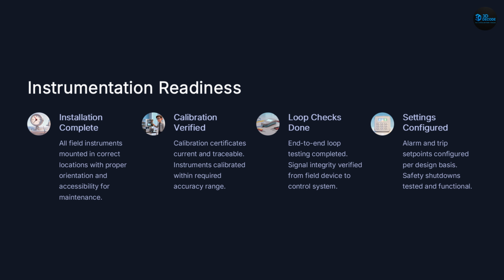instrumentation. The first requirement is installation. Every instrument must be mounted correctly, accessible, properly oriented, ready for operation. Then comes calibration. And this is where many FAT delays originate. A pressure transmitter may look perfect, but if calibration has expired, its readings cannot be trusted.